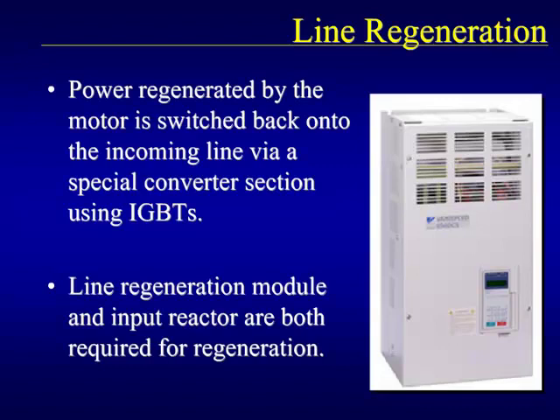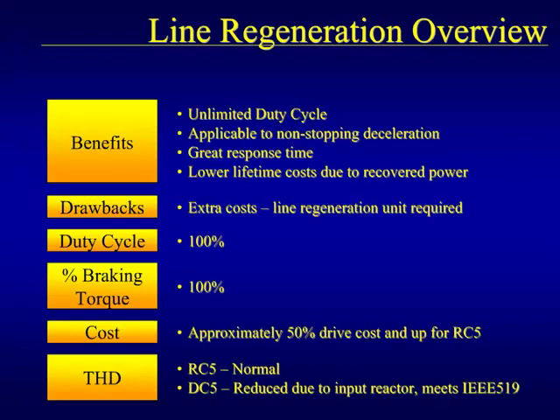A special type of braking called line regeneration is also available. As the motor regenerates during braking, the regenerated power is sent back to the drive's input power lines through an active converter using IGBTs. In order to use line regeneration, an additional line regeneration module and input reactor are both required. Except for the drawback of additional cost, line regeneration is by far the most superior method of braking. Because the regenerated power is transferred back to electricity and not heat, the duty cycle is continuous. Also, because the regenerated power is sent back to the power source, it can be recovered and actually reduce the lifetime cost of the unit.